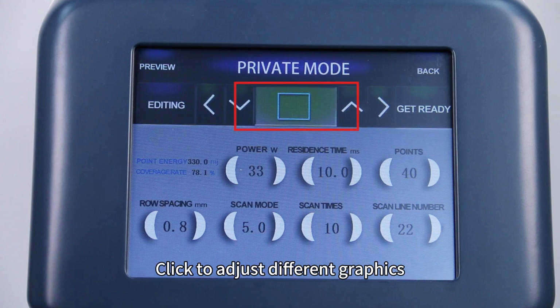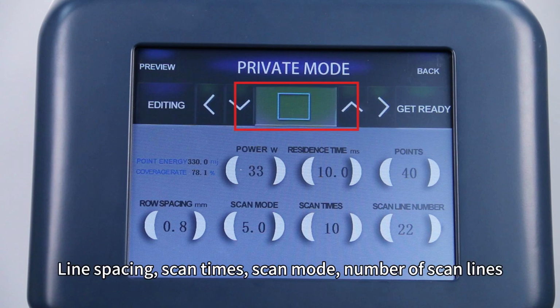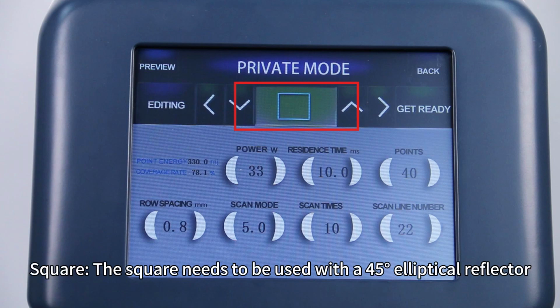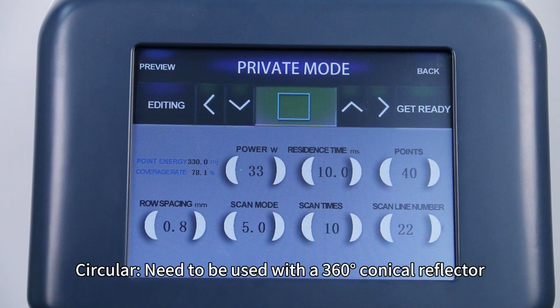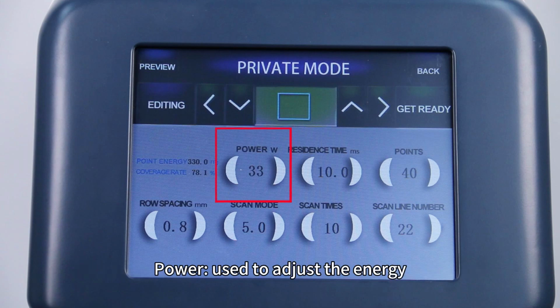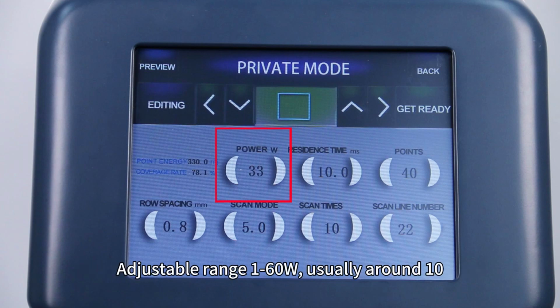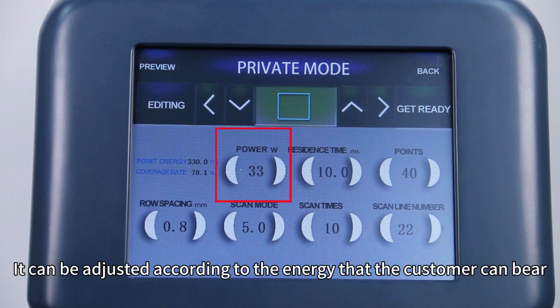Click to adjust different graphics, line spacing, scan times, scan mode, number of scan lines. Square: the square needs to be used with a 45° elliptical reflector. Circular: needs to be used with a 360° conical reflector. Power is used to adjust the energy. Adjustable range 1 to 60 watts, usually around 10. It can be adjusted according to the energy that the customer can bear.